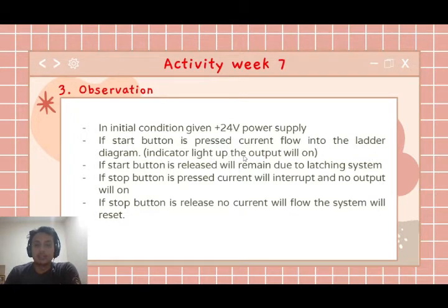The indicator lights up and the output will be on. If the start button is released, the output will remain on due to the latching system. If the stop button is pressed, the current will be interrupted and no output will be on. If the stop button is released, no current will flow, and the system will reset.